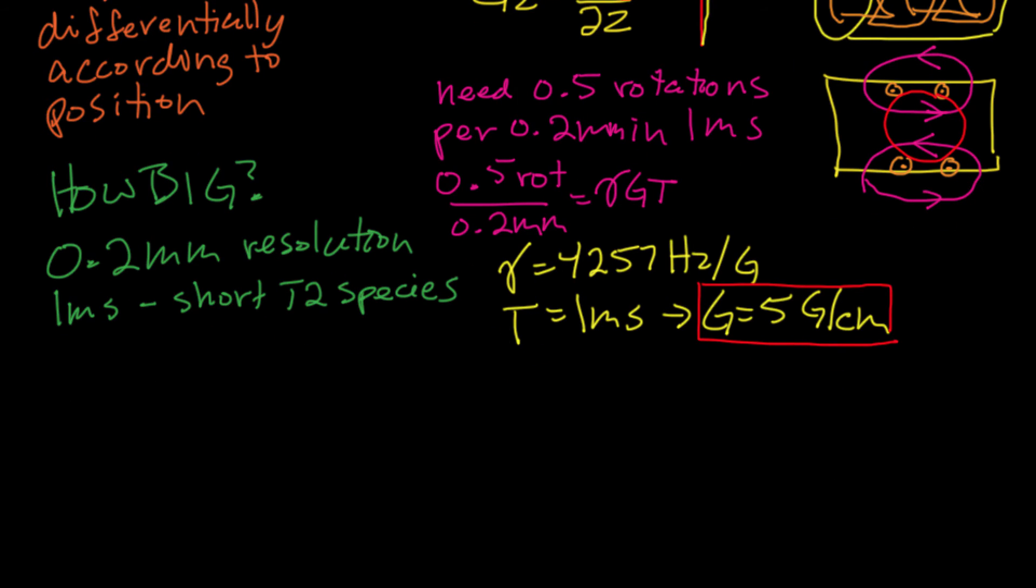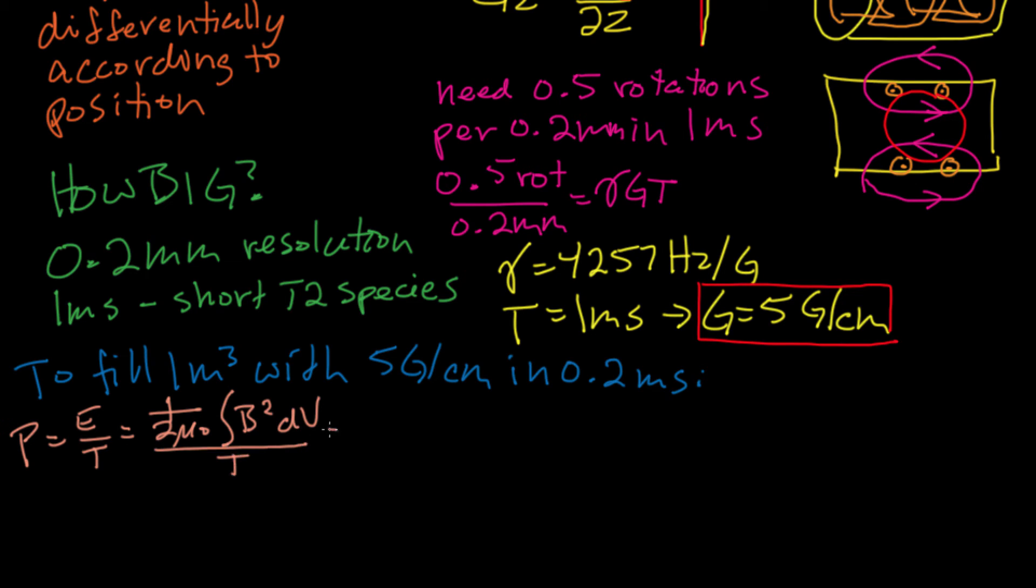Now taking a look at the power it takes to create such a gradient field. If we want to fill a cubic meter with 5 gauss per centimeter gradients, and we want to do that in about 0.2 milliseconds, so we want to ramp up in a time that's short compared to the pulse. The power required is the energy in the field over the time. The energy in the field is again the integral of B squared over the volume. Because it's a gradient field, we need to calculate the RMS value of a 5 gauss per centimeter gradient over that volume. But if you go through that arithmetic, you end up with a number that's about 500 kilowatts, so about a half a megawatt of power to get your gradients going in 200 microseconds. And this power requirement sets one of the limitations for how fast your gradient system can go.